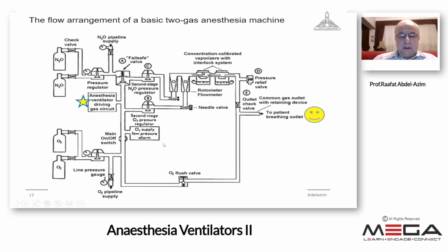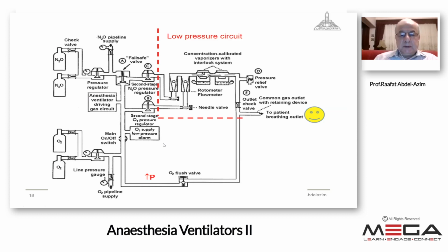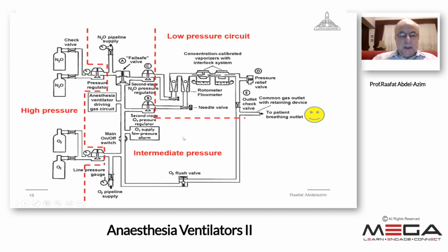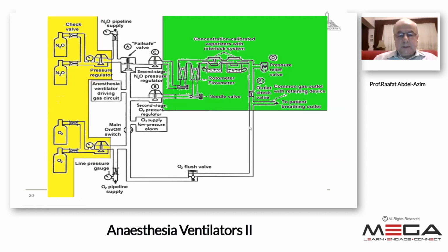I said that the flow arrangement in the anesthesia machine is divided into 3 parts of different pressures. The high pressure in the pipeline and oxygen cylinders, and the intermediate pressure, that is 4 bar inside the machine, that's used in different areas. And our concern now is about the ventilator, so it is operated by oxygen at a pressure of 4 bar or 4 atmospheres. After that, the oxygen is subject to second stage reduction, reaching just above 1 atmosphere to go through the flow meter, vaporizer and the fresh gas outlet. These are the different pressure areas.